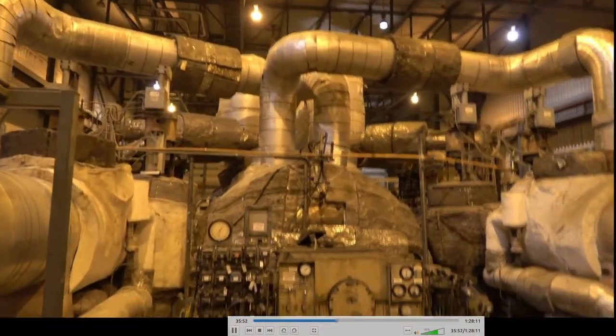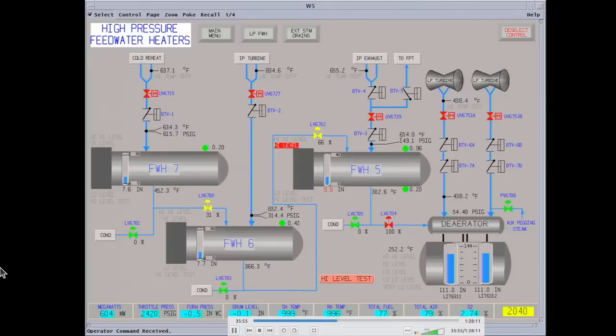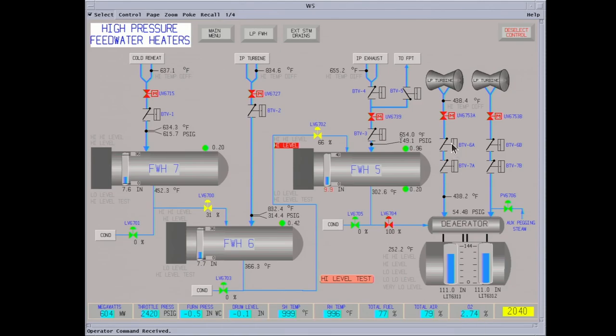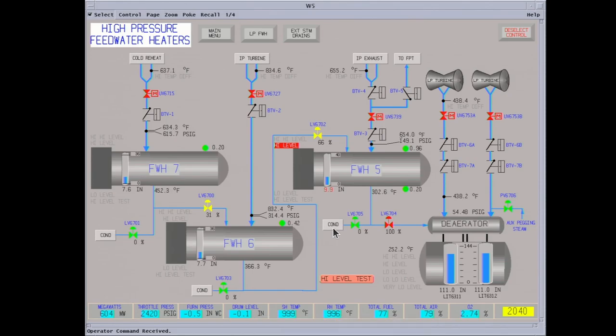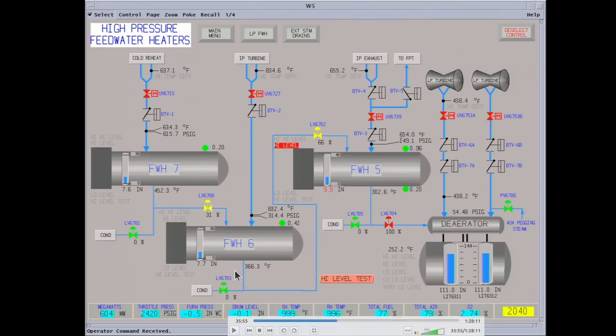These are some of the trip circuits for vacuum and lube oil pressure. Here are your high-pressure feed water heaters 5, 6, and 7 — the deaerator is considered in the circuit. These are your BTVs — bleeder trip valves — critical for preventing steam from these feed water heaters from flashing and going back in to drive the turbine to overspeed if it trips offline. These block valves will close if you have high level in your feed water heaters. The drain valve opens, the upstream shuts off, and it starts dumping.